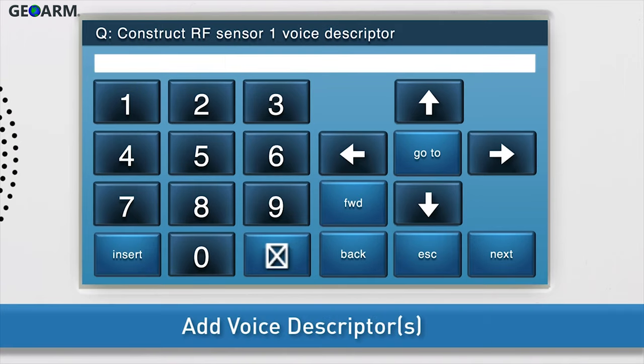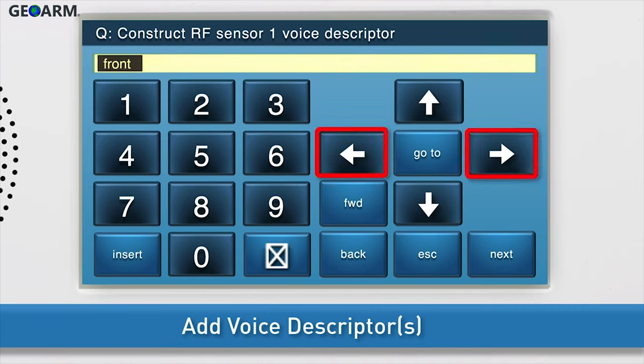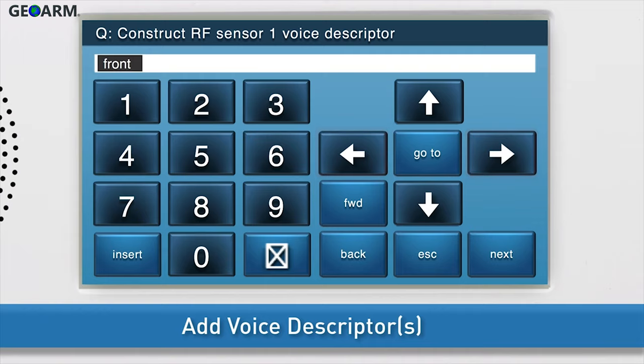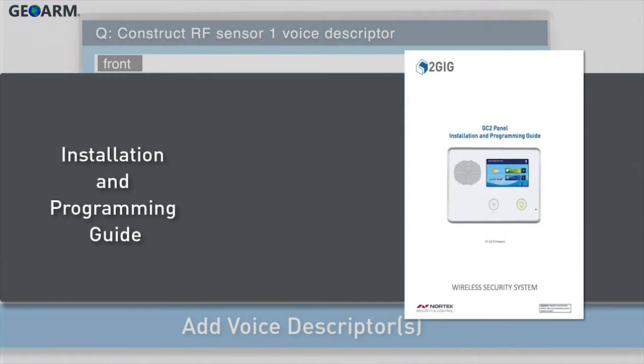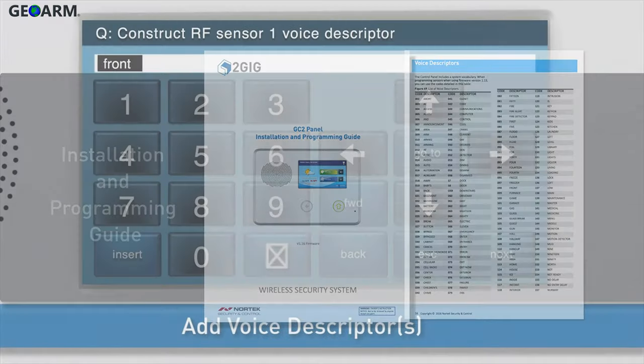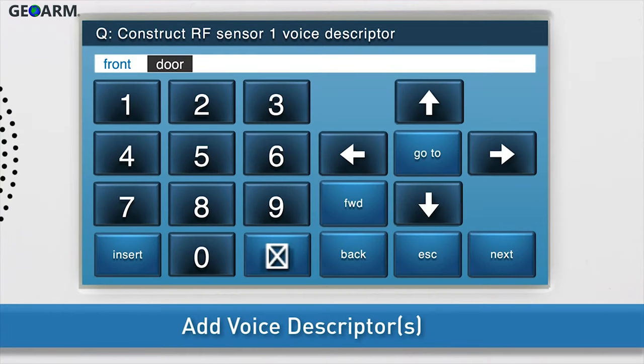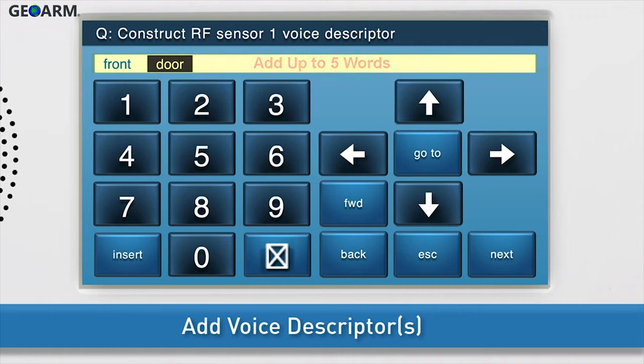Next, add the voice descriptors. Press Insert. The word abort will automatically appear in the answer box. Change the word by either using the right and left arrow buttons, or by typing the word's three-digit code using the keyboard. For a list of all voice descriptors and their associated codes, see the installation and programming guide. To add another word, press Insert again and repeat the steps just discussed. You can add up to five words. Once the desired word or words displays in the answer box, press the down arrow to go to the next sub-question.